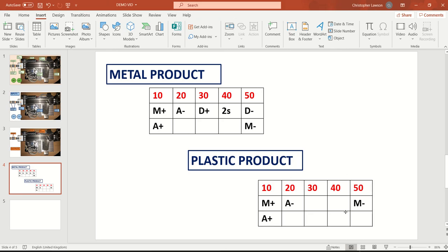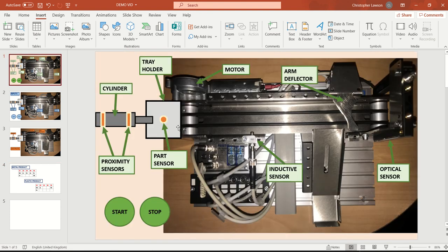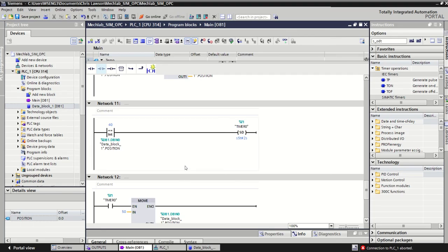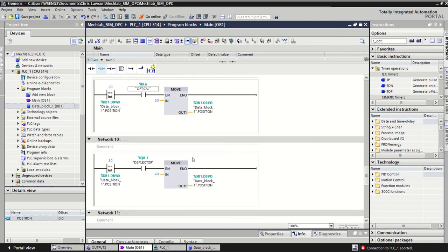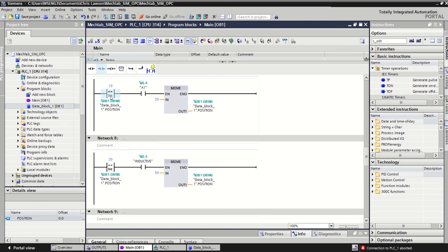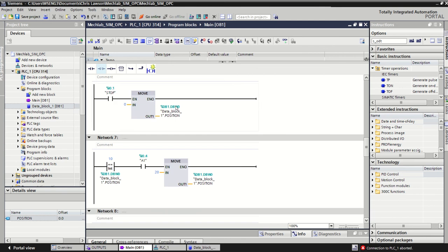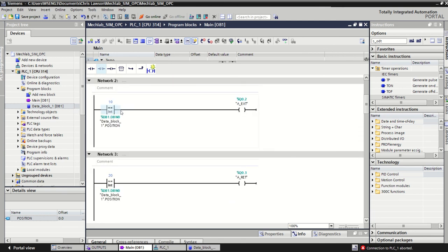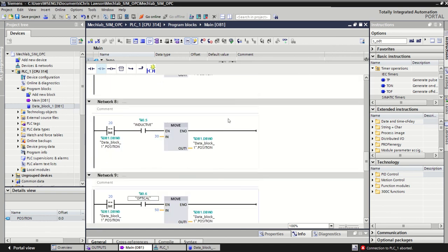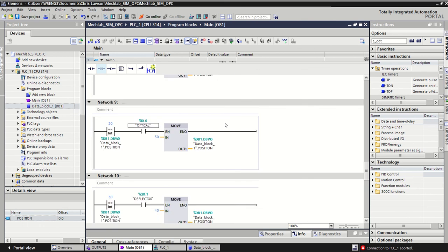And again, hopefully you can see, I know the inputs aren't really listed here, but you can use this to understand how it works, along with the context of the hardware that you have there. I've gone over many ideas about how we keep our code linear with ladder logic by using these step numbers. Basically the inputs generate the step number, they move the value into that position block, and then the outputs just basically, if you're in that position block, then you trigger the output. So the step numbers are the link between your inputs and your outputs. And it keeps code nice and linear, you can follow a good pattern, and it's got very good fault finding techniques.